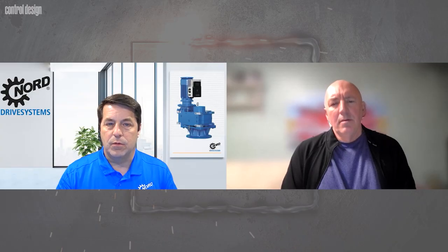And then we have problems where the cables can be too lengthy running from the VFD to the motor, right? That's a cable length situation that's covered by the National Electric Code. So you run into some complexity there. Moving it out near the motor gets rid of that problem and shortens that cable length. That's expensive cabling. You could save on the wiring related to that.